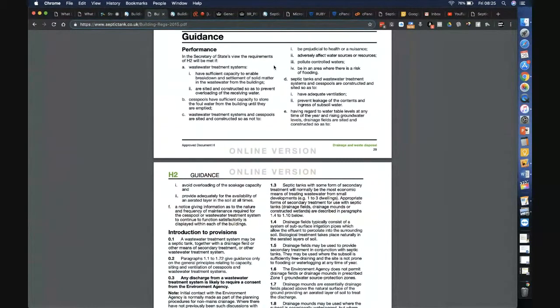So this is talking about domestic units now. Let's give you an example of that. Let's say your house is producing 1,000 litres a day. The inhabitants are producing 1,000 litres of liquid wastewater a day. British Water have come up with the figures that you need about 2,000 litres as a rough dilution rate. So if you were sizing a tank based on the house producing 1,000 litres a day, then you'd need a minimum of a 3,000 litre tank.